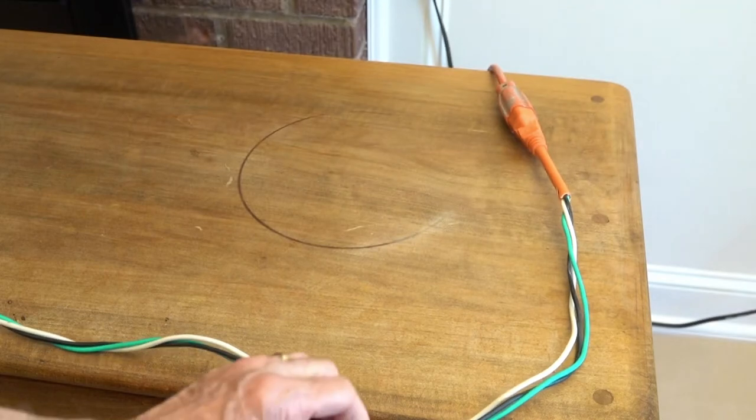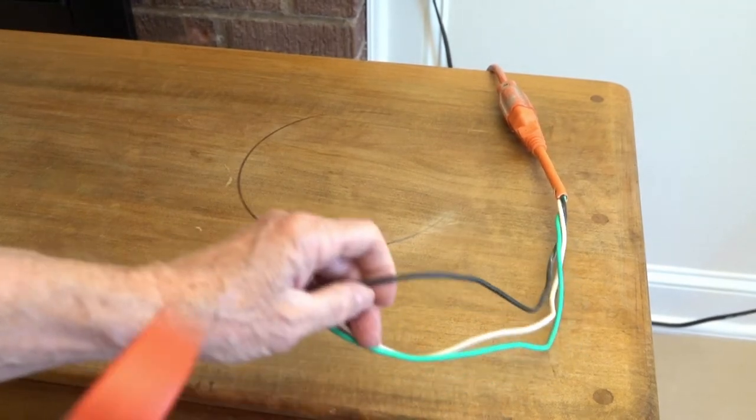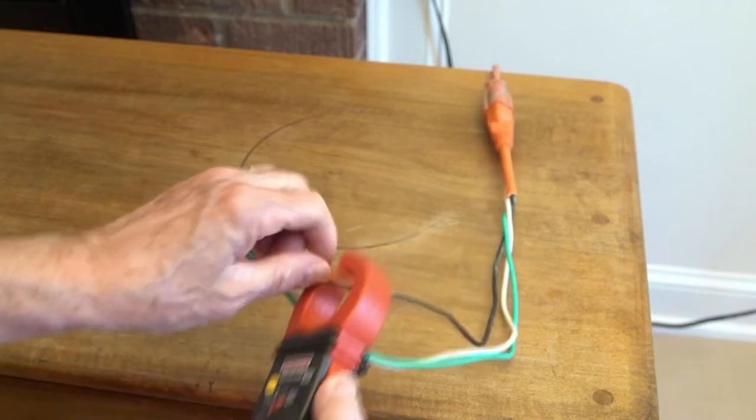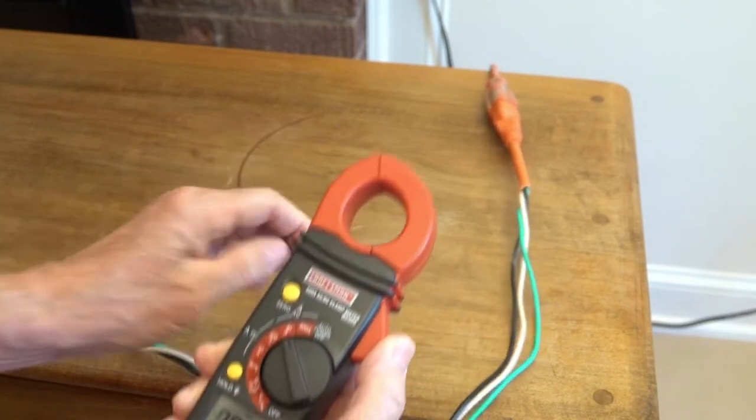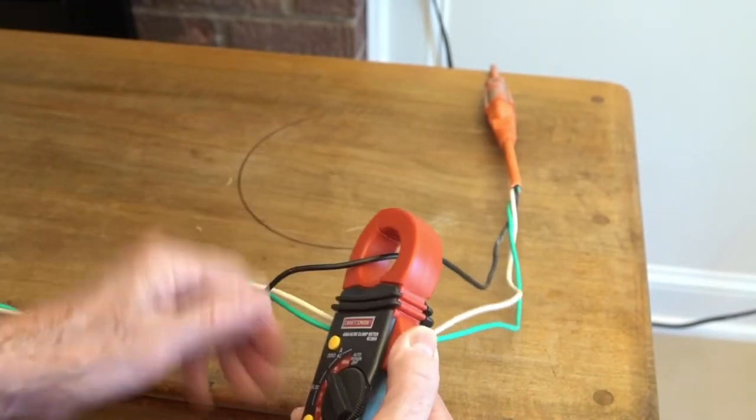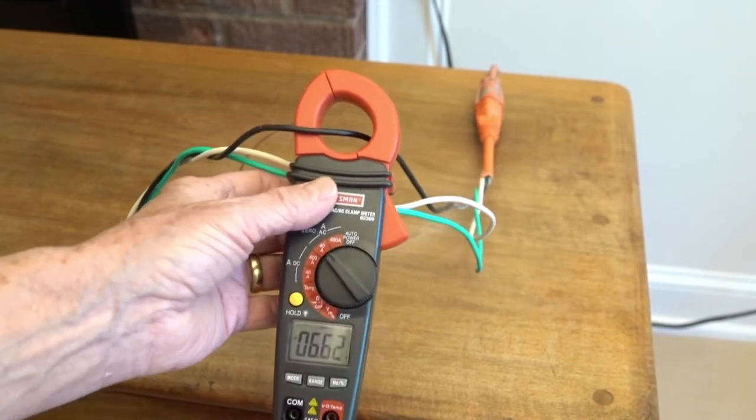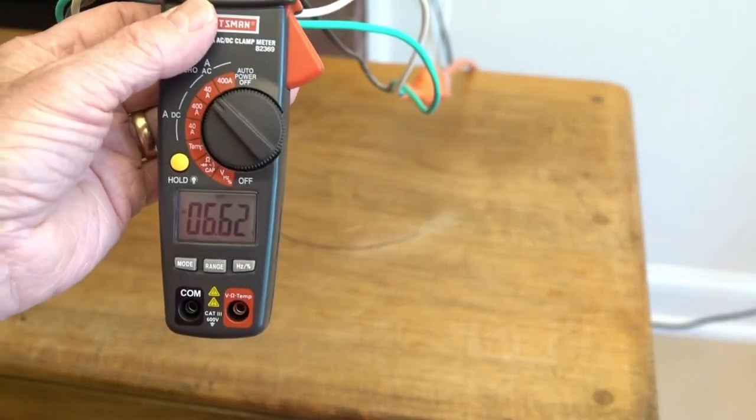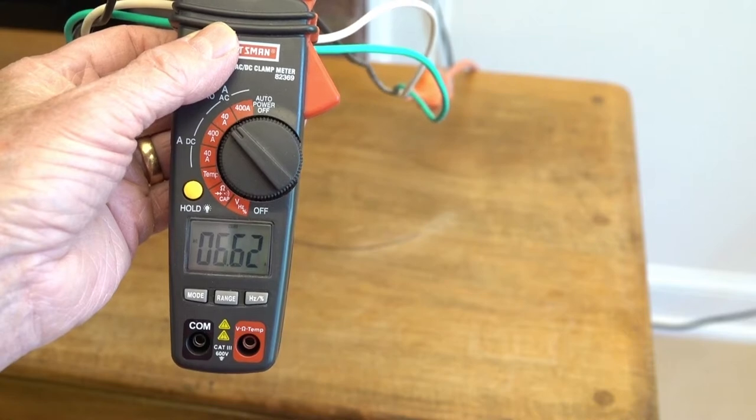Okay, we're hooked up to a thousand watts of halogen work light. We'll just clamp this. Let's zero this first. Okay, here we're on the black lead, just normally the hot lead. We can see that we're at 6.62 amps.